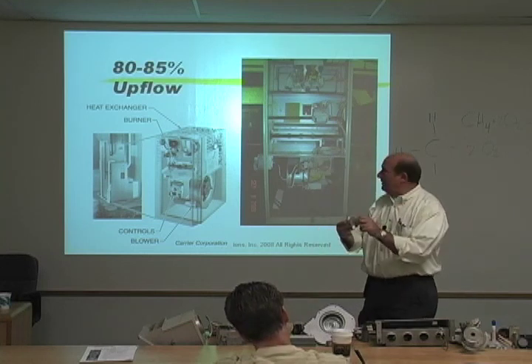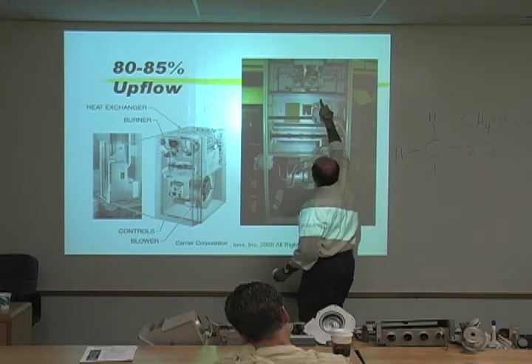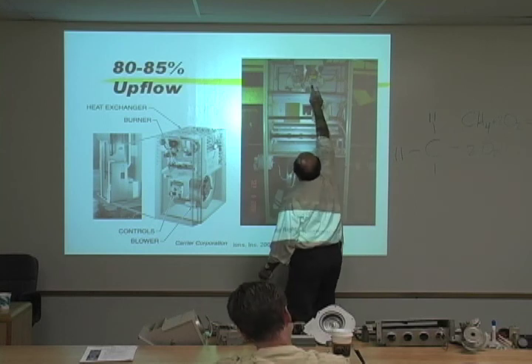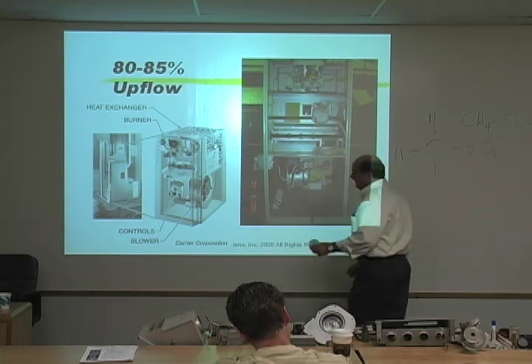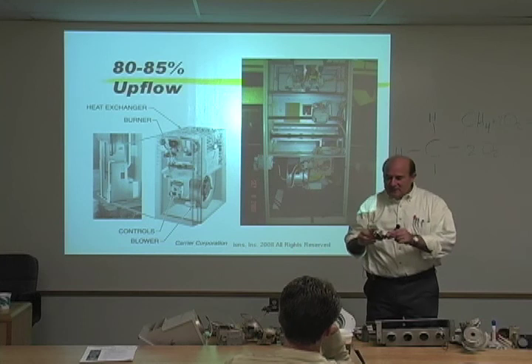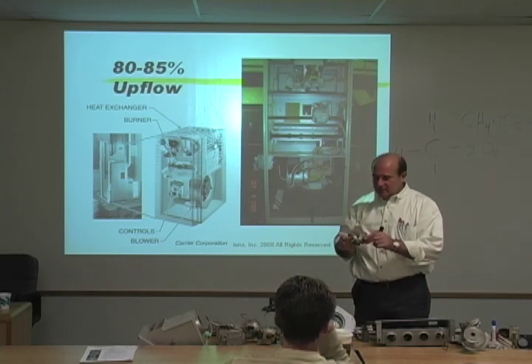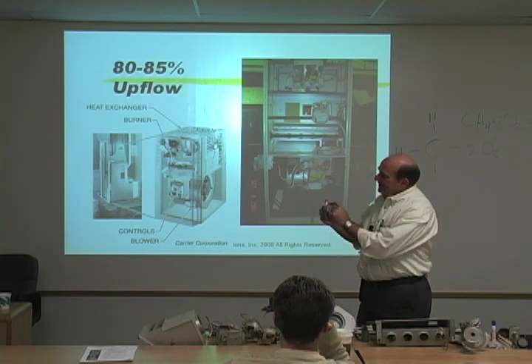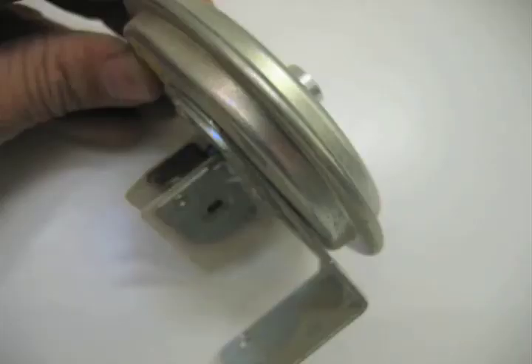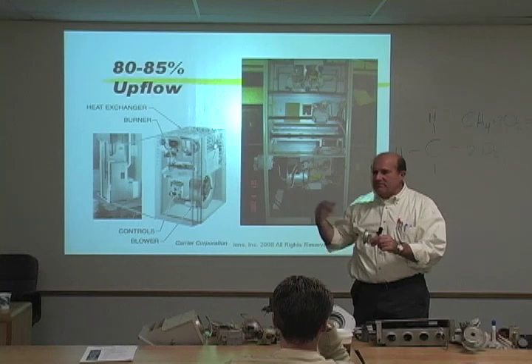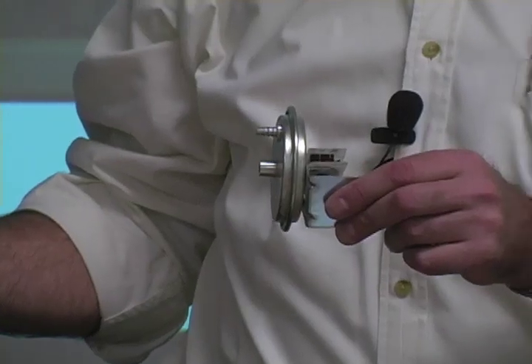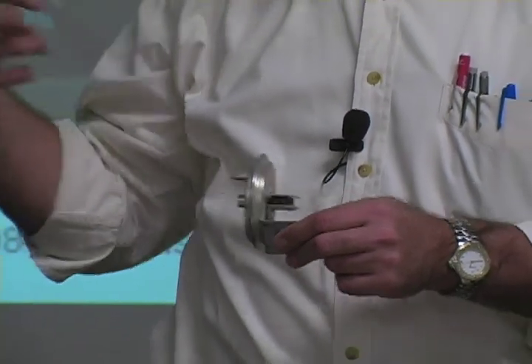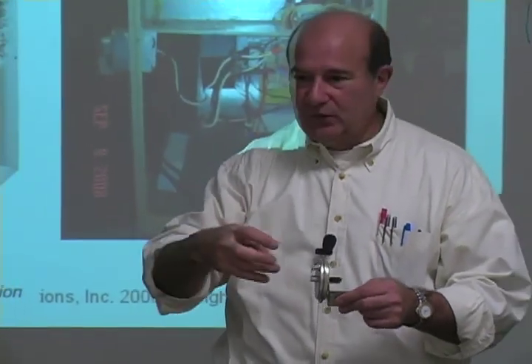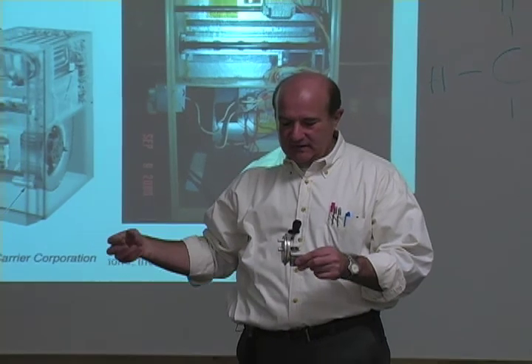Now this switch will be mounted in the furnace, and this one, it happens to be, let's see how I can do it, right up at that location there. And what this does is it tells the main, it's got a set of contacts in it. It's just a switch that is normally open. And when the combustion blower comes on, the fan assist comes on, it creates a negative pressure inside the heat exchanger. It's drawing air and fuel mix into the heat exchanger.